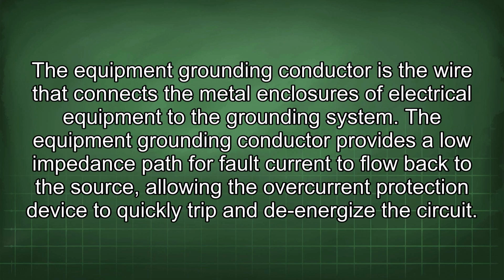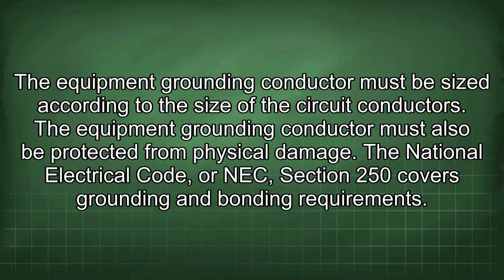The equipment grounding conductor is the wire that connects the metal enclosures of electrical equipment to the grounding system. The equipment grounding conductor provides a low impedance path for fault current to flow back to the source, allowing the overcurrent protection device to quickly trip and de-energize the circuit. The equipment grounding conductor must be sized according to the size of the circuit conductors. The equipment grounding conductor must also be protected from physical damage.